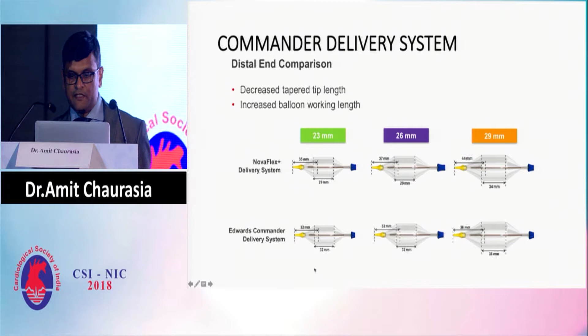Let me just introduce you to the system. This is the lumen to which the guide wire comes. This is for balloon inflation, and there is an indicator of how much volume should be there in the inflation device for each valve. This is the indication for the default place where you start after you have loaded the valve, and this is the balloon locking mechanism, and this is one for the fine adjustment, and this logo tells you that this portion should be up while you are pushing the delivery system inside. There is an indicator for how much flexion you have made at the distal tip, so you can keep track of that.